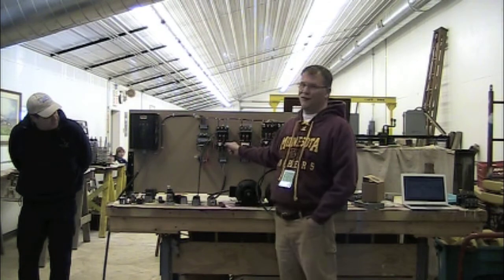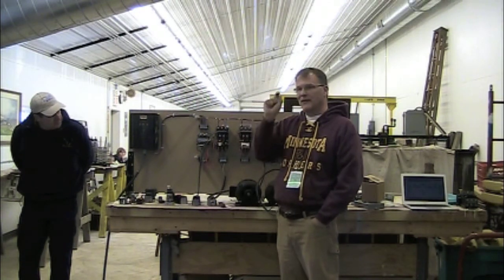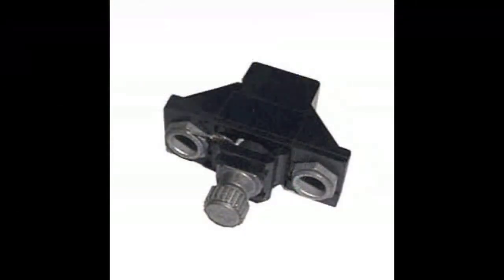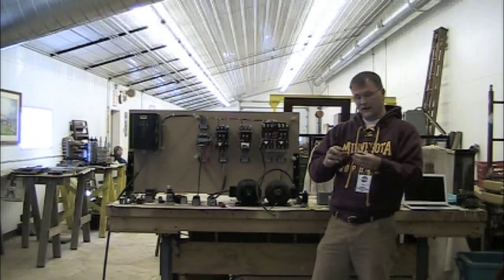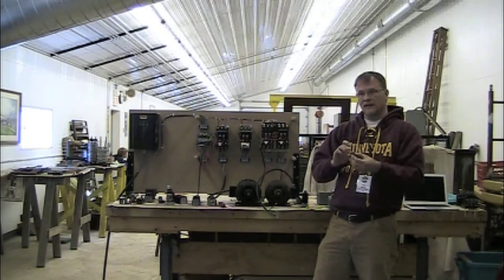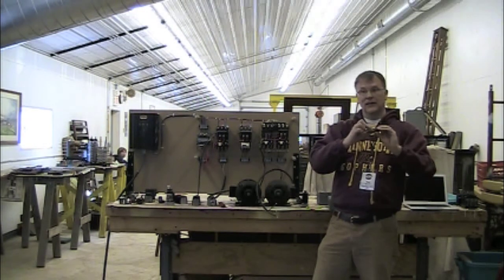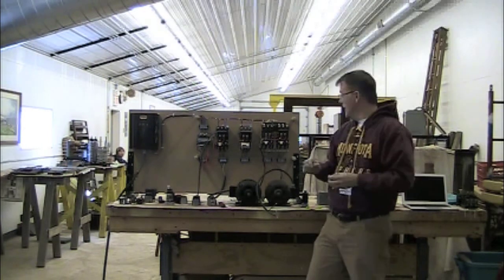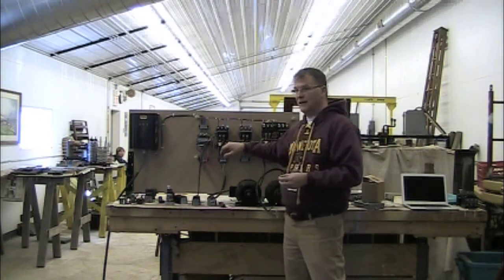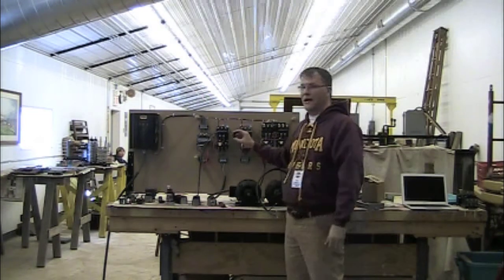So these are eutectic overloads. What these are is a little brass barrel, filled with a eutectic alloy that has a very specific melting point. There's a shaft through it and a little ratchet wheel on it. This is the end of the spindle, and it's designed so that the heater values. This is just a little coil of wire, and these are all specifically designed so that at a certain current, the temperature of this is going to go up. It's going to melt that solder, release this little barrel, and this thing is going to spin free, and that's going to then trip this overload block. A lot of people look at these things like they're some kind of fuse element or whatever.